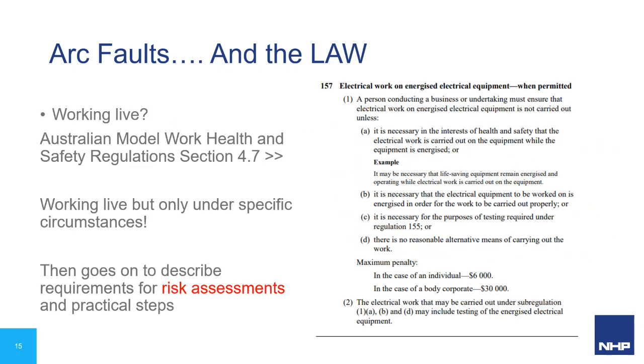In the health and safety regulations, section 4.7, regulation 157 actually gives you some guidelines on this. The very important thing here is it's saying, don't do it. And then it lists the exceptions, but note the exceptions as well. Testing purposes: sometimes you need to test things while they're live. That makes sense. You have to carry out some of those tests on live equipment, by the nature of them working while you're testing them. Life-saving equipment: obviously there are some medical applications that need to still be running while you're working on them. Or if they need to be energized to be worked on, or if there's no reasonable alternative. It is a bit grey there, saying what no reasonable alternative means.